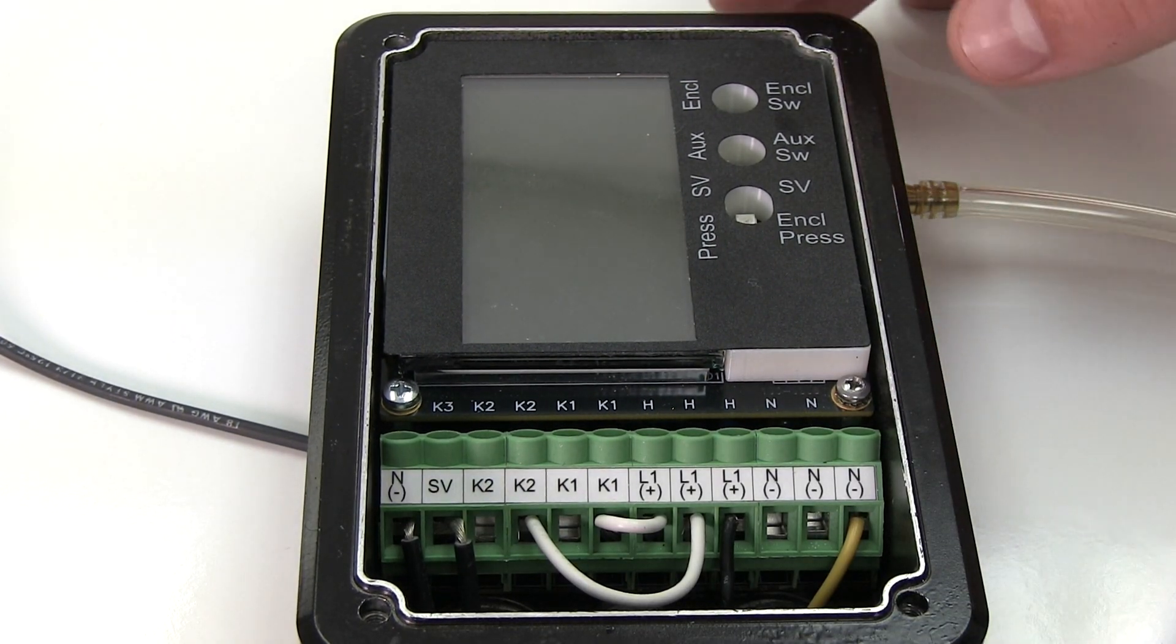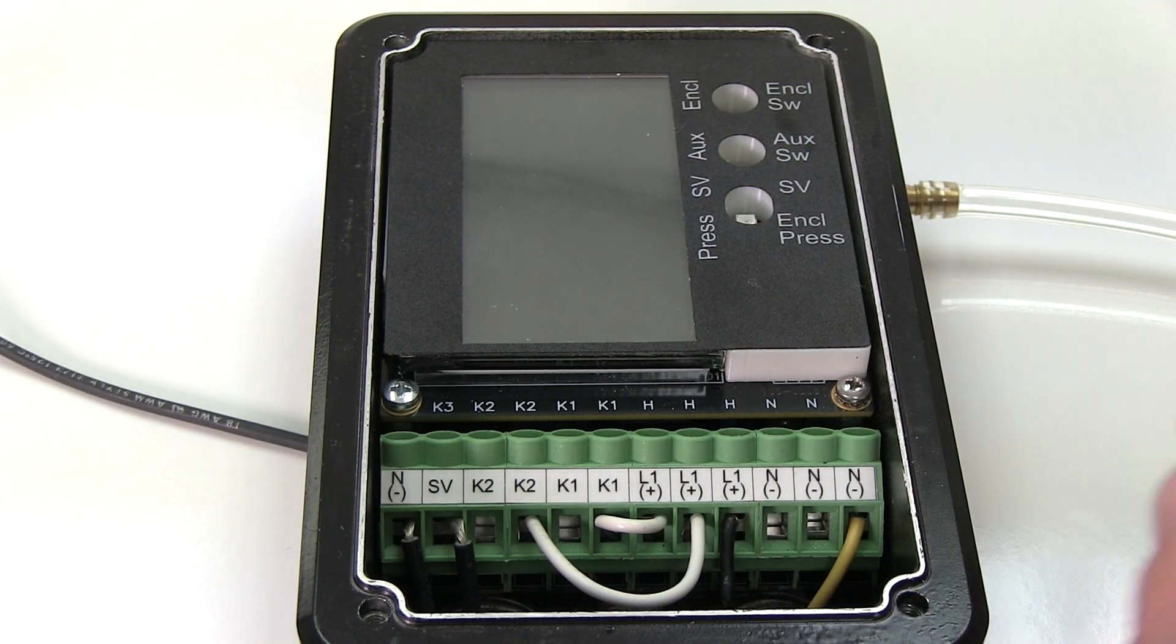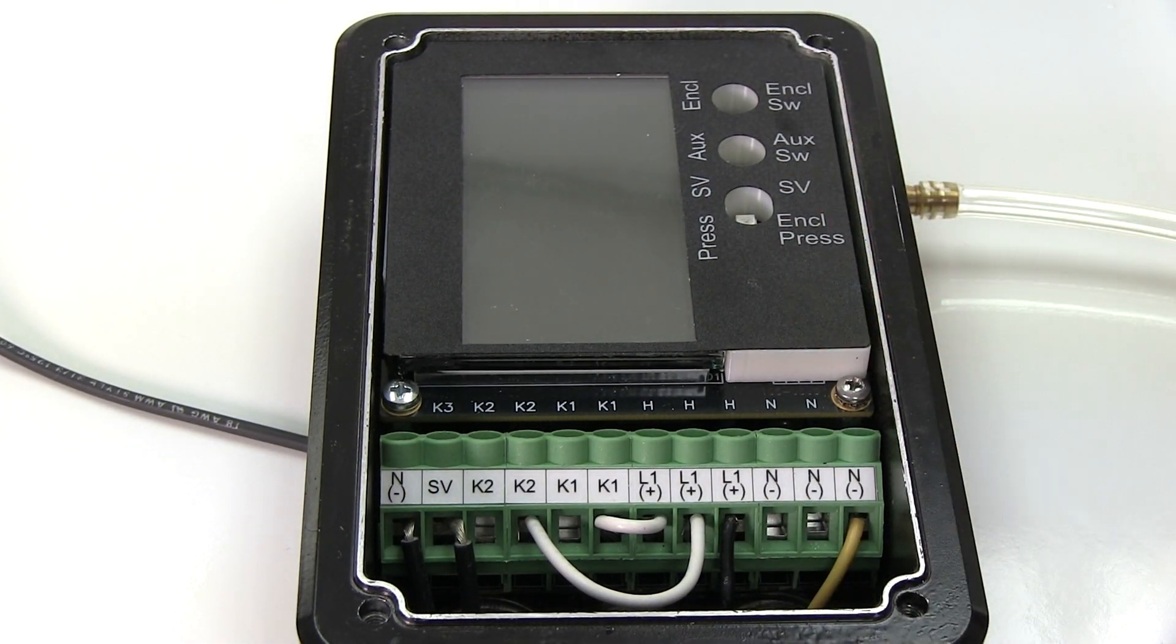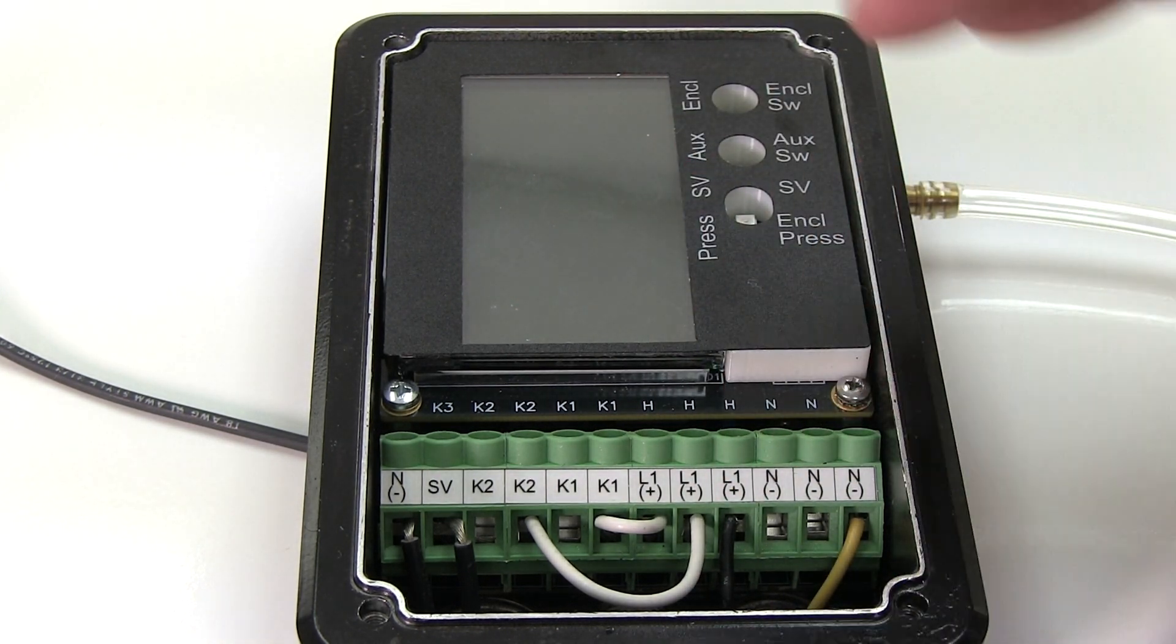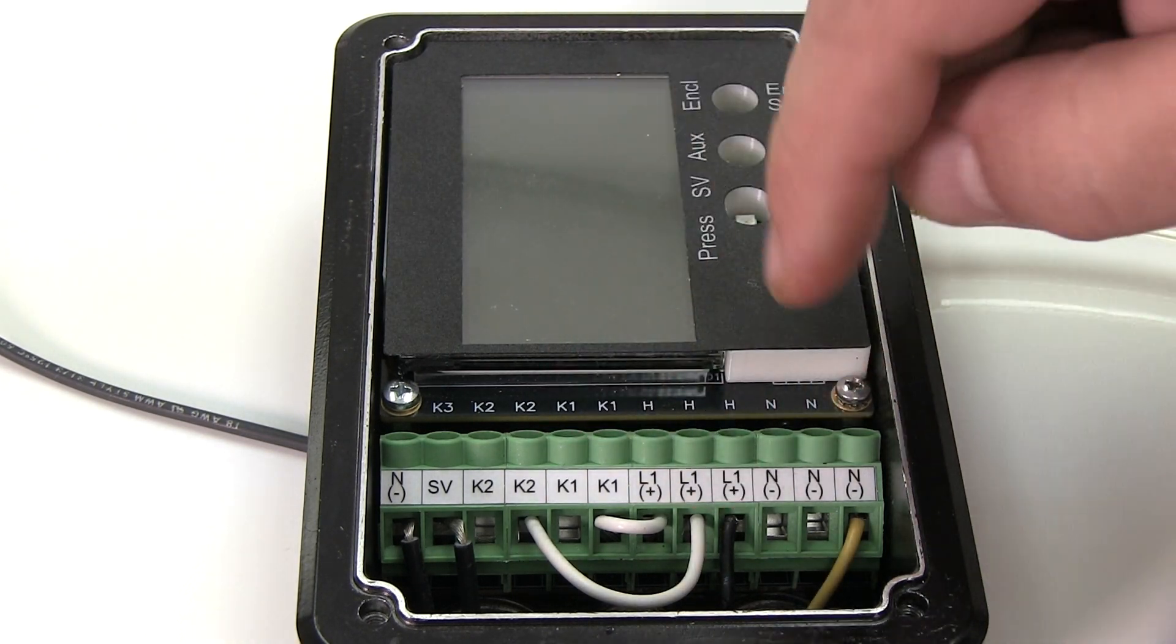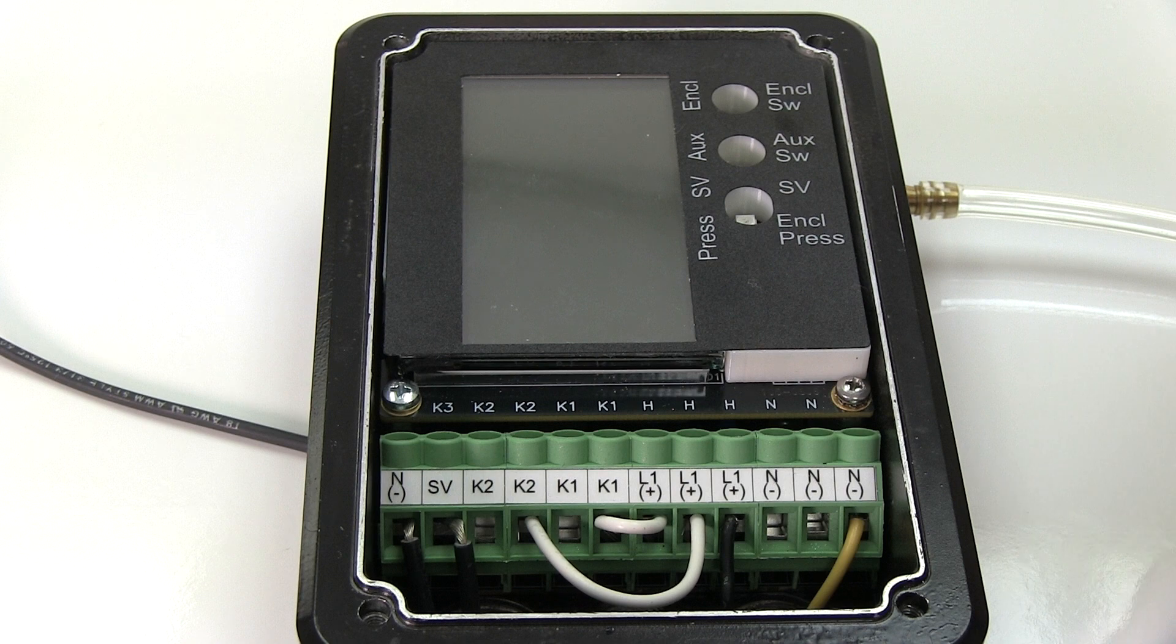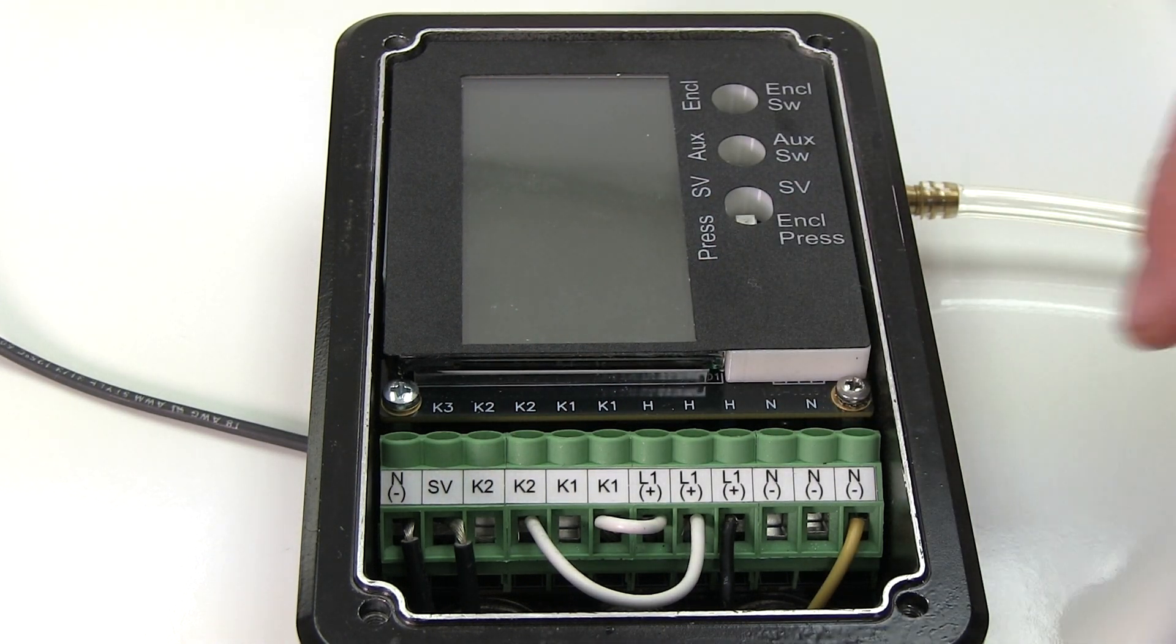So really, that's how you get the initial setup for the 7500 wired up. Now I have power to my enclosure through the L and N contacts. I have the control unit to be energized. And then I have the power jumped over to my K1 contact, which is my enclosure power contact, and my K2 contact, which is an alarm contact.